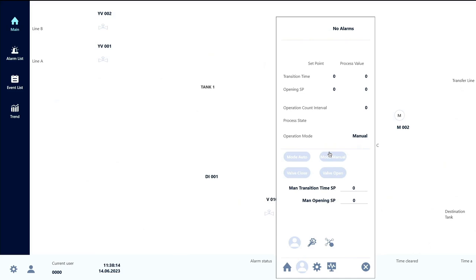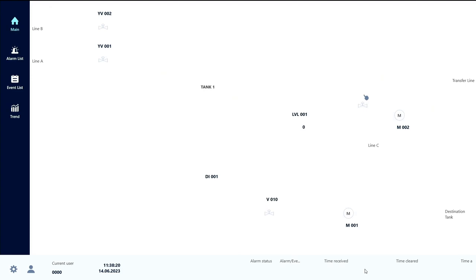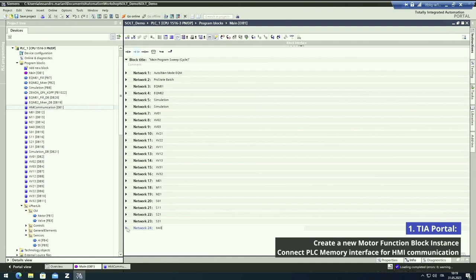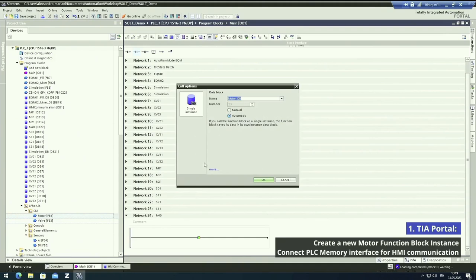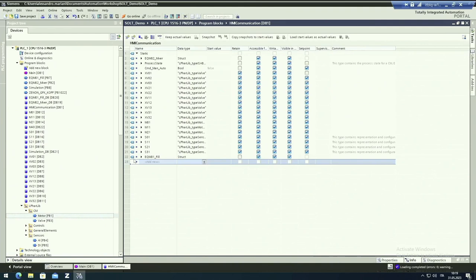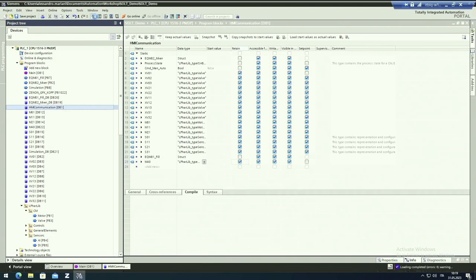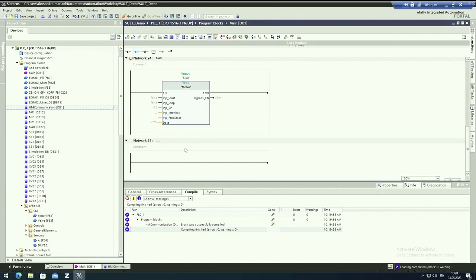Now starting the video — we can do the same with the TIA Portal. It's the same technology. We had a function block in OB1 for communication. We instantiate a new object — this time a motor. We need to connect the variable. In a global DB we put the data type library — this type is a structure of the motor type. I flag it as retained, compile it. I go to the main, set which type of communication I want, and download to the PLC. The PLC part is finished.